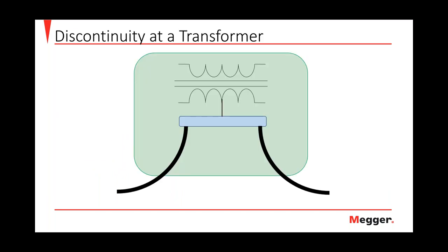So what do we mean by that? If we view this as a discontinuity at a transformer, here we have our transformer. This is the cable coming in, going to a load break elbow on a feed through bushing or pass through bushing, and then the cable coming out. And this is our concentric neutral shields that are coming off and are bonded to the grounding system.